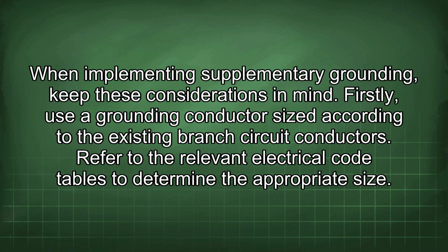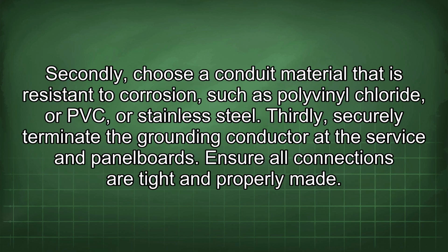When implementing supplementary grounding, keep these considerations in mind. Firstly, use a grounding conductor sized according to the existing branch circuit conductors. Refer to the relevant electrical code tables to determine the appropriate size. Secondly, choose a conduit material that is resistant to corrosion, such as polyvinyl chloride, or PVC, or stainless steel. Thirdly, securely terminate the grounding conductor at the service and panel boards. Ensure all connections are tight and properly made.